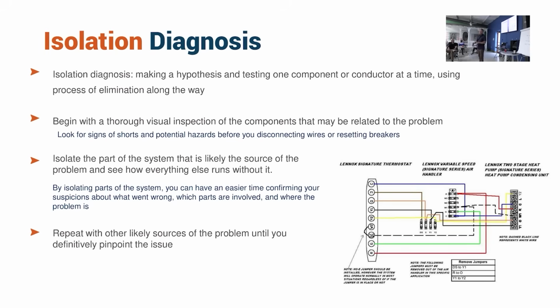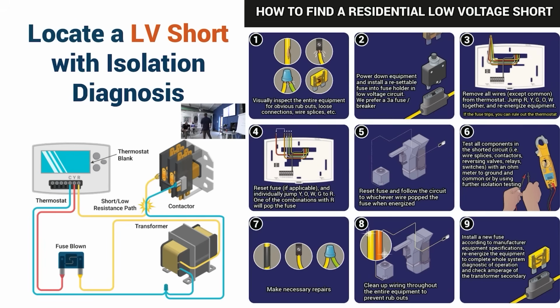Once you get to the point where you've done all your practical visual inspections, now you want to do isolation diagnosis. Some of this has changed over the years, but I want to cover it with low voltage, because this is one of the areas guys struggle with the most. Now, if it's a communicating system it's a little different—you have to follow the best practices. We're going to talk about communicating systems, VRV, VRF tomorrow; Jordan's coming in and we'll cover that more in that section. But for now, we're going to assume it's a 24-volt system you're working on.